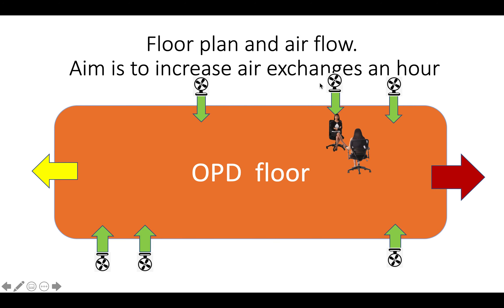This is the floor plan of my OPD clinic. The front two fans shown in the previous picture face the waiting area, with consultation, optometry, and examination rooms on the sides and in the back. Six green arrows show where we have positive forced pumping of outside air into the hospital. We have passive outflow shown by the yellow arrow from the main door, and in the back a giant 24-inch exhaust fan that pumps air out of the building into the back garden.